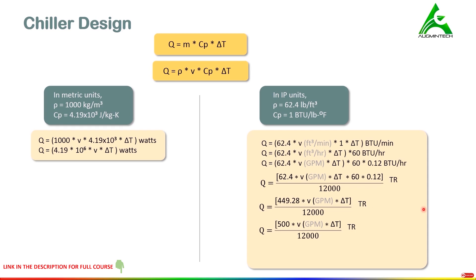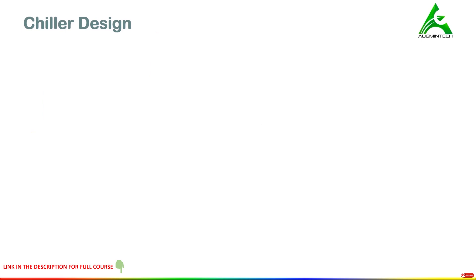The most commonly used equation in the industry is in SI units and in IP units. Finally, this can be simplified further as V × delta T divided by 24. It is very important to note that V must be substituted in gallons per minute and the final answer will be found in tons of refrigeration.